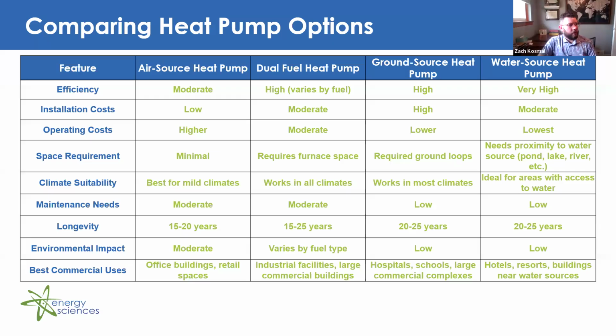So next, space requirement. Your air source heat pump will typically take up the least amount of space. Dual fuel heat pumps, kind of the same deal, but that dual fuel component of it can be a backup furnace or a boiler. So more equipment just requires a little bit more space. Now for those ground source heat pumps, your main space requirement will be that ground loop, right? So if you have a large field next to your facility, that may be a great opportunity to install a ground source heat pump. Or another example may be you have a large parking lot adjacent to your facility, and maybe that'll need to be repaved in the next few years, and you've got to tear up all that concrete. That may be a great time to install a ground source heat pump system under that parking lot. Okay. So these are things to consider when you're doing other infrastructure projects as well.